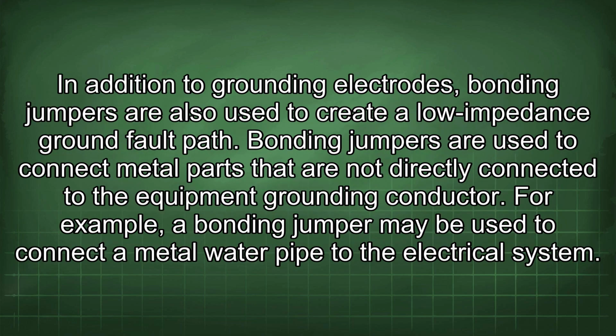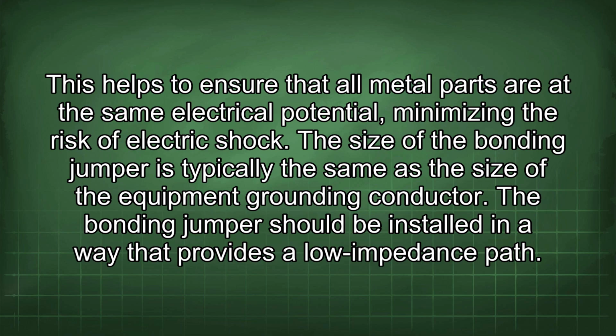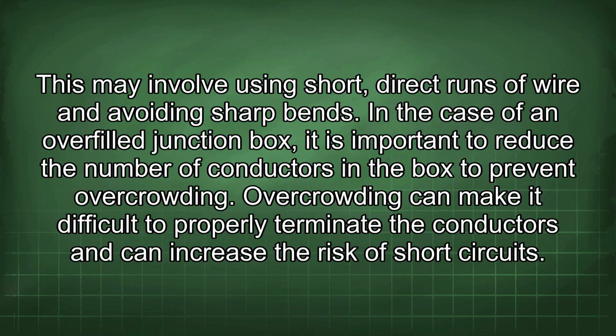In addition to grounding electrodes, bonding jumpers are also used to create a low impedance ground fault path. Bonding jumpers are used to connect metal parts that are not directly connected to the equipment grounding conductor. For example, a bonding jumper may be used to connect a metal water pipe to the electrical system. This helps to ensure that all metal parts are at the same electrical potential, minimizing the risk of electric shock. The size of the bonding jumper is typically the same as the size of the equipment grounding conductor. The bonding jumper should be installed in a way that provides a low impedance path. This may involve using short, direct runs of wire and avoiding sharp bends.